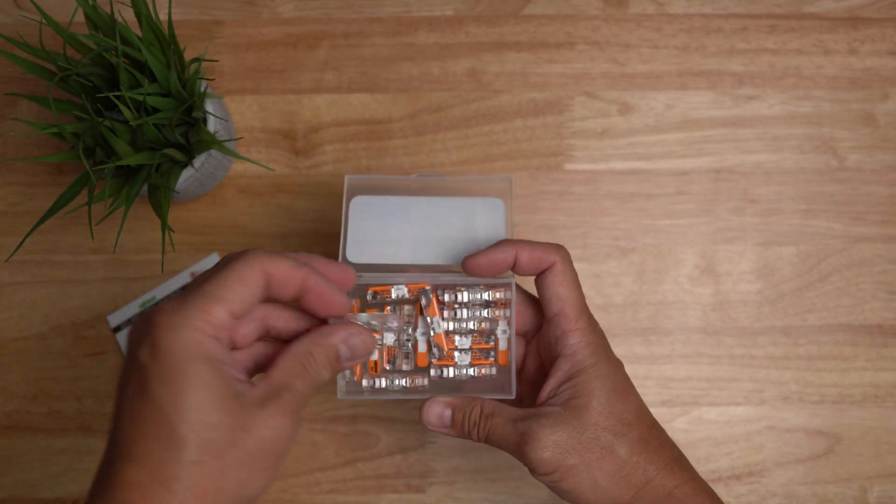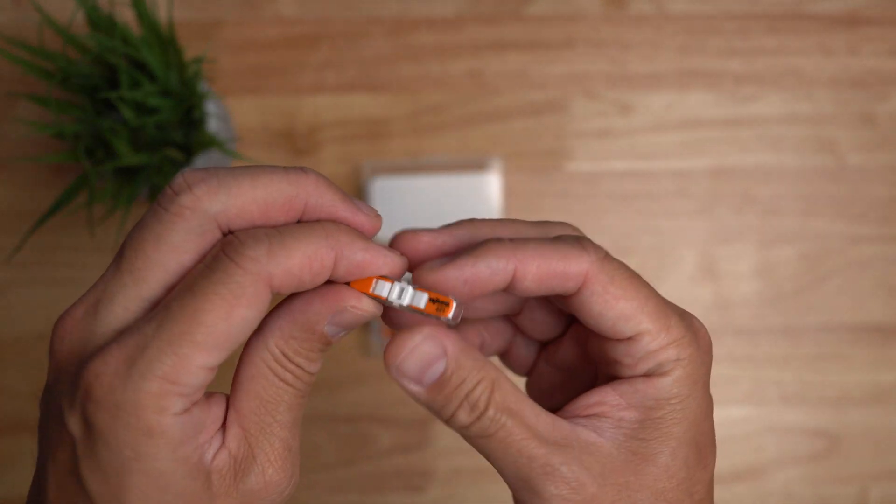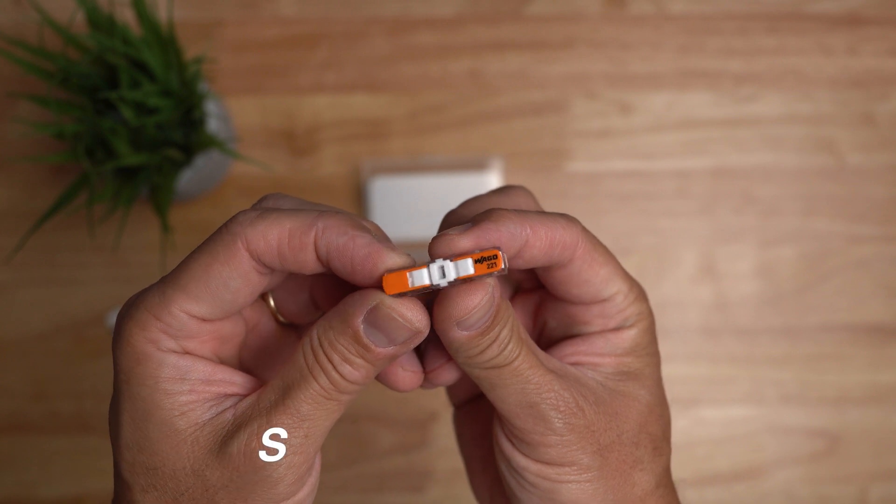One thing I like about this WAGO connectors is that it can connect solid or stranded wires and with this particular inline model also can connect from 20 to 12 gauge solid or 18 to 12 gauge stranded wires.